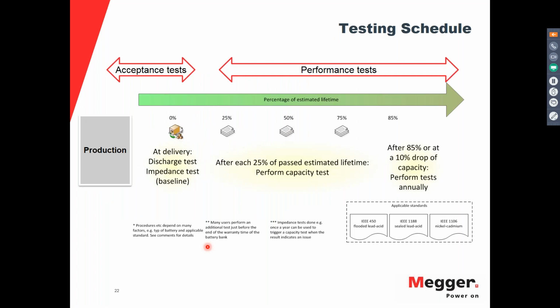The idea is that you perform an acceptance test at the manufacturer's facility or at the site once it is installed, and around the time of installation, usually somewhere between installation point and 6 months. And then within the first 2 years of the life of the battery, you run the performance test. You run another capacity test. And from that point on, you perform the test every 25% of the life of the battery.